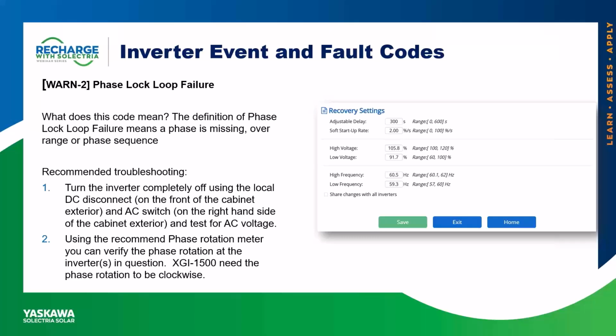When the inverter is fully energized for the first time, you close both AC and DC, or the inverter goes through a restart, meaning you power cycle it or it's recovering from a fault. At that point, the inverter goes through a 5-minute UL countdown. It will observe and adhere to the recovery settings parameter window, which you can see on the screen here. For VAC specifically, the range I mentioned will fall between the high voltage and low voltage set points. This brings us to our next recommended troubleshooting step.